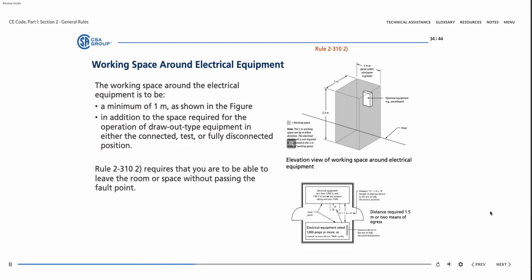However, due to the higher electrical ratings of the equipment, of 1200 amperes or more, when operating at 750 volts or less, or any ampere rating when operating at over 750 volts, the fault currents are also much higher, and therefore, to allow individuals in the room or space to exit safely, Rule 2-310-2 requires that you are able to leave the room or space without passing the fault point. This usually means there are to be 2 exits from the room or space.